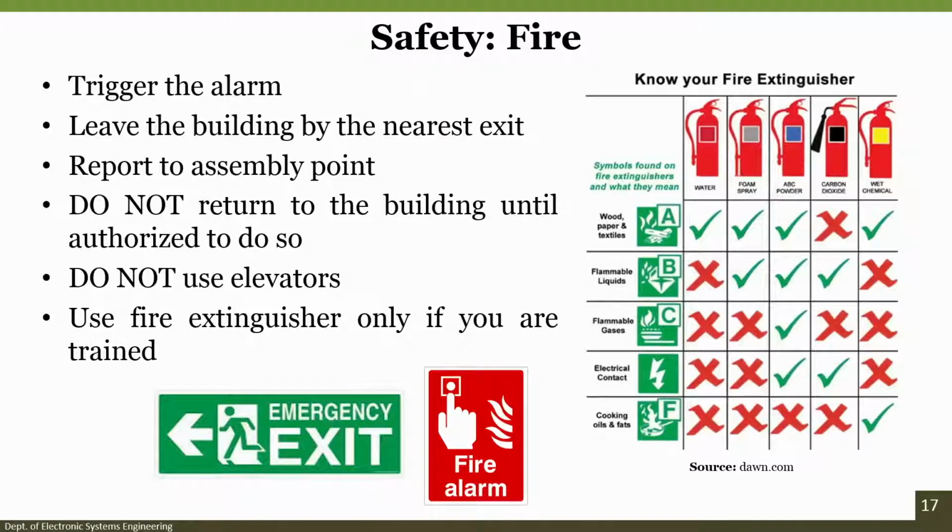Okay. So, another one is fire safety. Most labs would have a fire extinguisher. You should know that there are several kinds of fire extinguishers, for example water, foam spray, ABC powder, carbon dioxide and wet chemical. Depending on the fire, if wood or paper is burning, you can use all of these fire extinguishers except carbon dioxide, because carbon dioxide will further enhance the flaming.